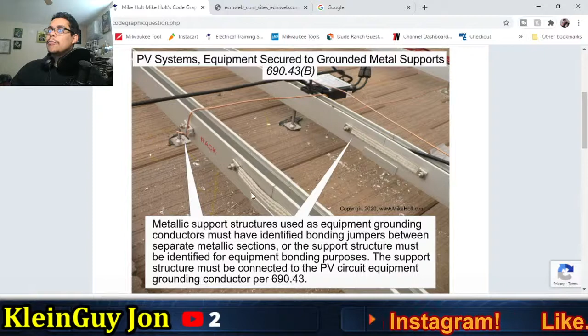This graphic is based on the 2020 NEC, about PV systems equipment and securely grounded metal parts, per 690.43. Metallic support structures used as equipment grounding conductors must have identified bonding jumpers between separate metallic sections. This is all about photovoltaic systems - you definitely have to ground and bond all metal parts, with approved bonding jumpers on the metallic support structures.